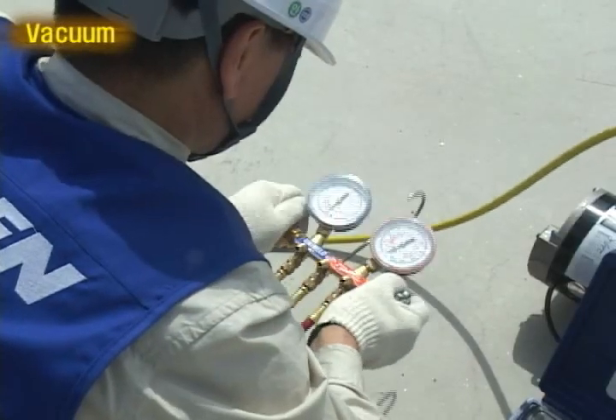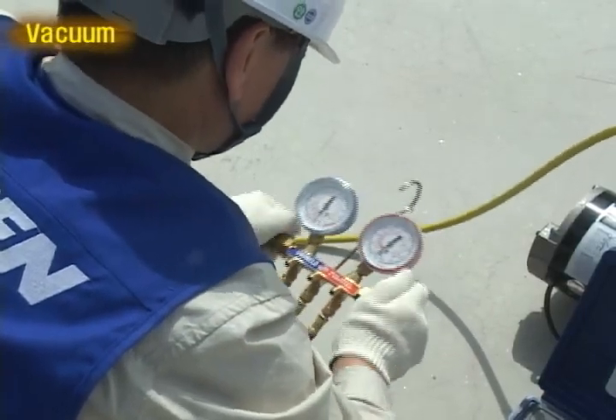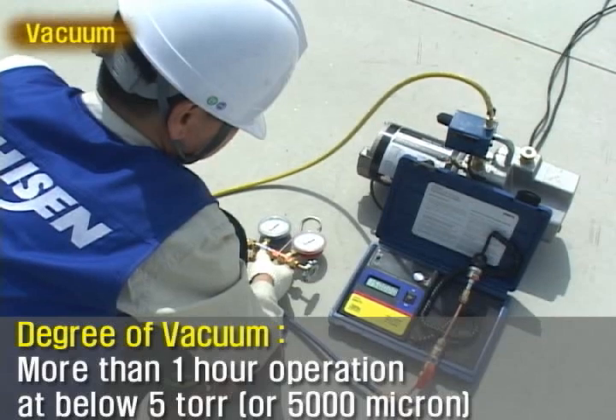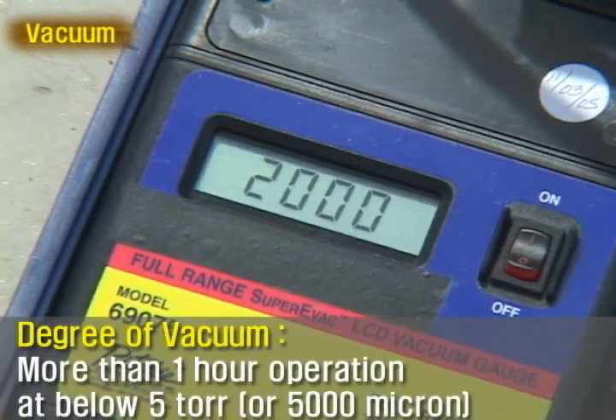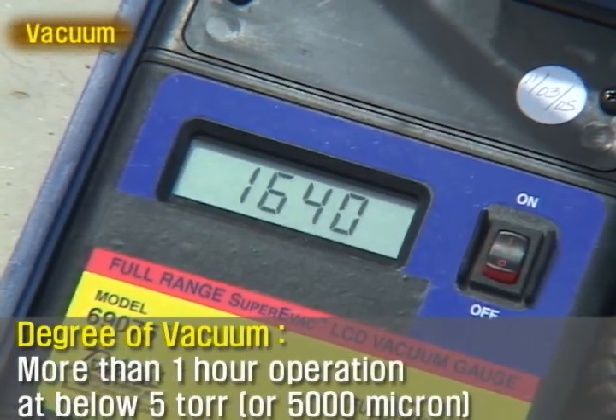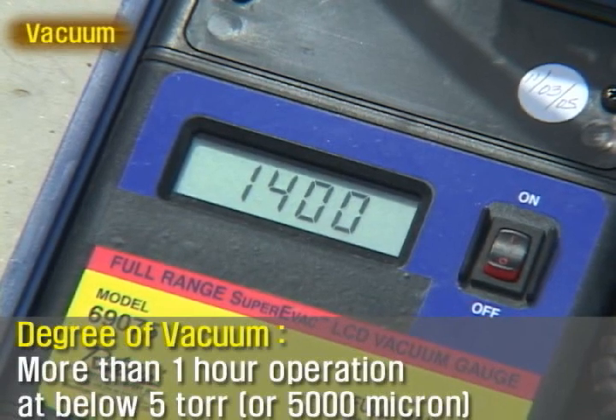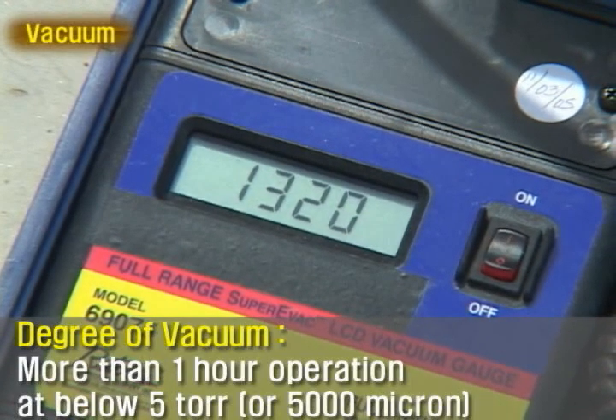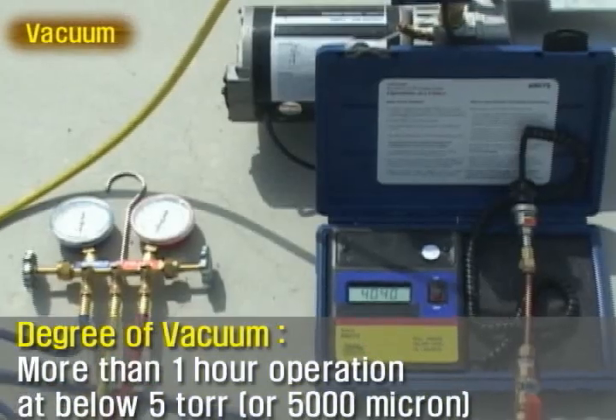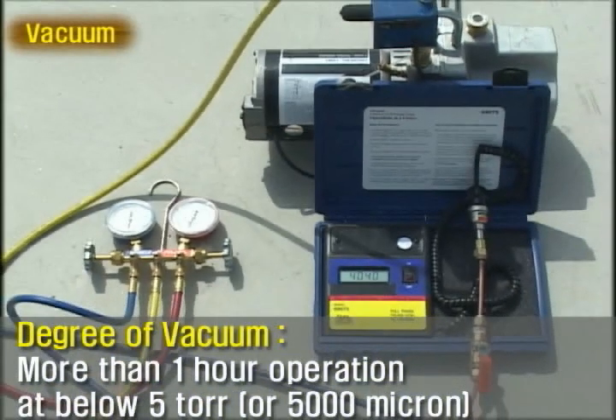After the vacuuming degree has lowered to 5 torr or 5,000 micron, then 1 more hour of vacuuming is done. If it does not reach 5 torr, it means there is a leakage or moisture, which should be cleared and re-vacuumed. It is more convenient to check leakage with a digital vacuum gauge.